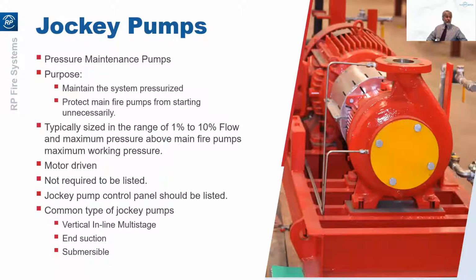Jockey pumps. These are pressure maintenance pumps, usually quite low flows, 5 or 10 gallons a minute. The purpose is to keep the system pressurized and from leakage past the system or somebody opening a valve and letting a little bit of water out, perhaps to wash down something. You don't want your big 1,500 gallon a minute or bigger fire pump kicking in just for that. So you have a jockey pump to keep the system pressurized. There is no requirement for these to be listed. There frequently would be an ANSI pump or possibly a vertical inline pump. Very commonly, it would be a Grundfos segmental ring pump. So although the pump doesn't have to be listed, the control panel does. It needs to have a listed control pump panel.